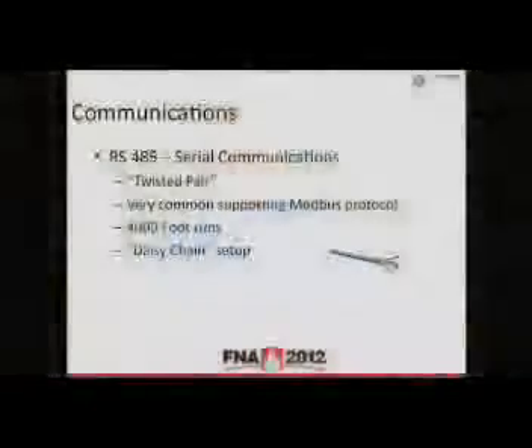So why do that? Well, you look at a couple things. All right, if I'm using a communication protocol to gather information from an instrument, I could be using RS-485 or Modbus communications, and I'm getting not only what the actual temperature is, but I'm getting the set point. I might be getting the percent output. I'm getting all your I/O associated to that particular control. You might also be able to take the additional program information. So if it's actually running a recipe, all of that information can be brought in. So that's valuable information when you're looking at taking advantage of not just producing a chart for the quality department, but now you're looking at troubleshooting from a maintenance standpoint or looking at the operational statistics of a controller.